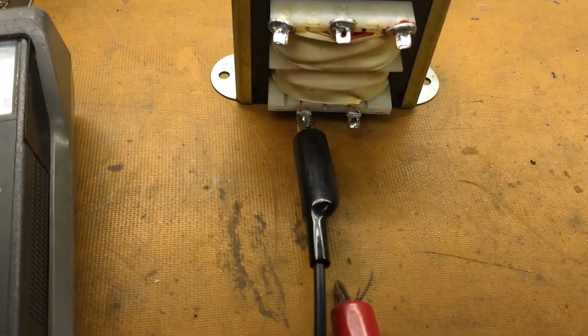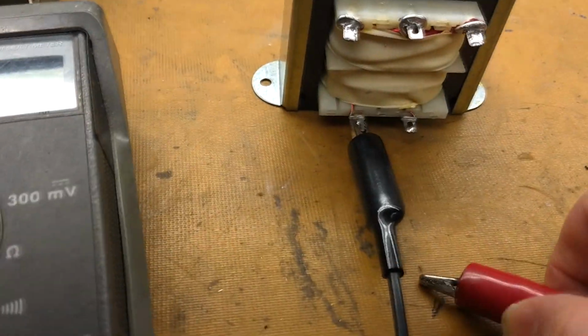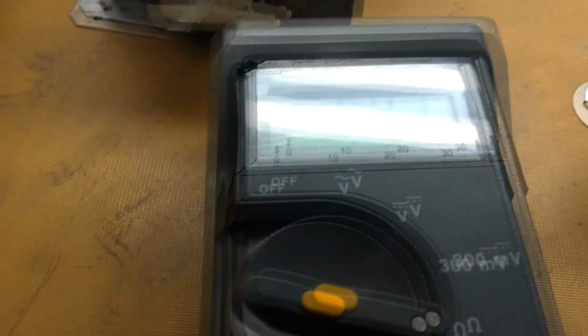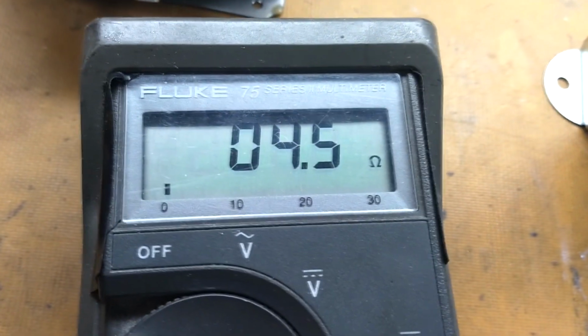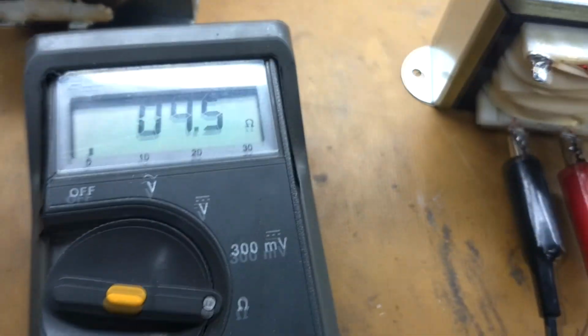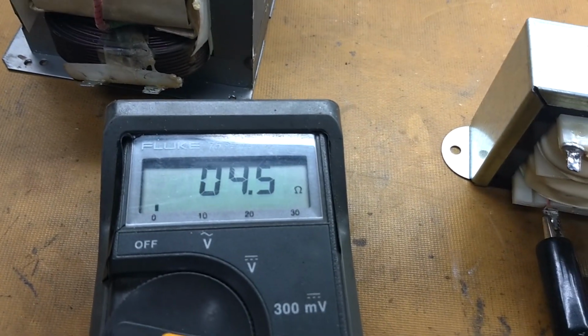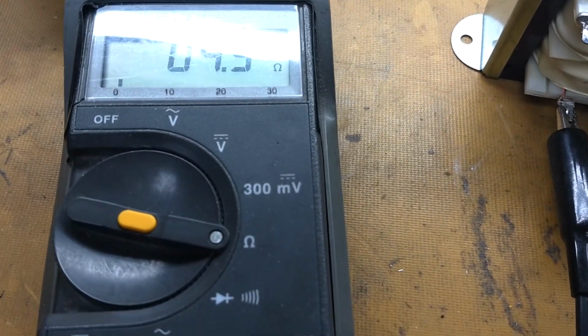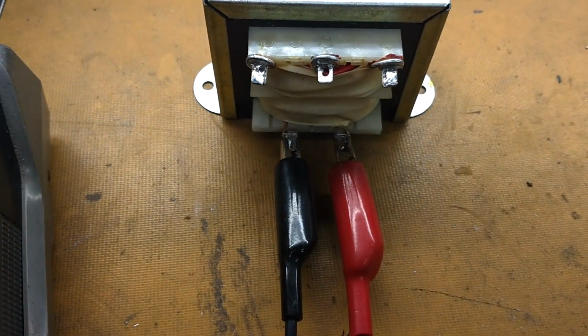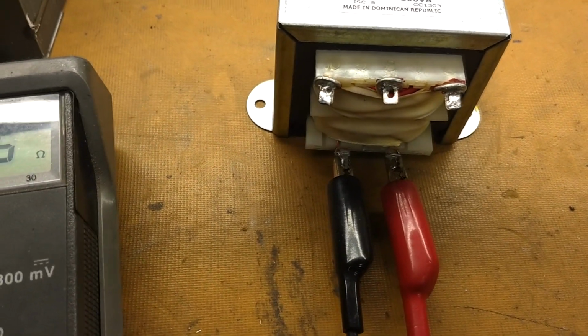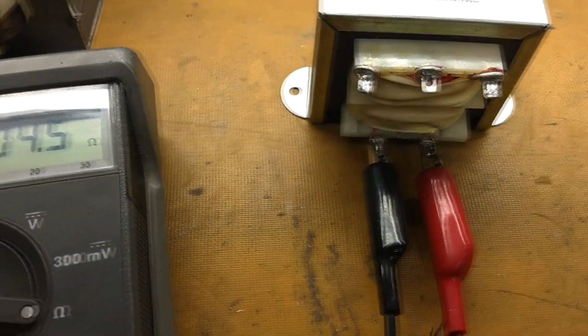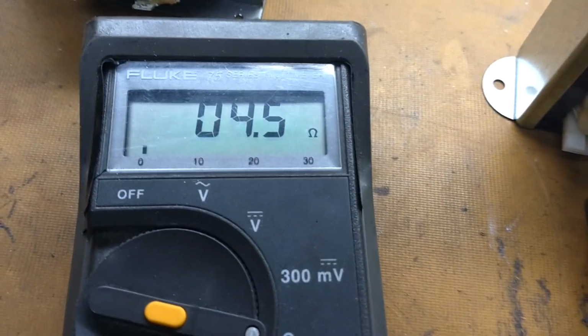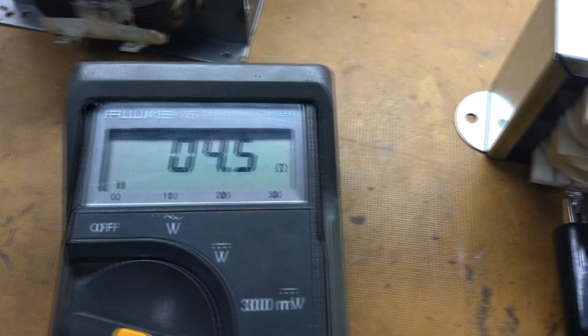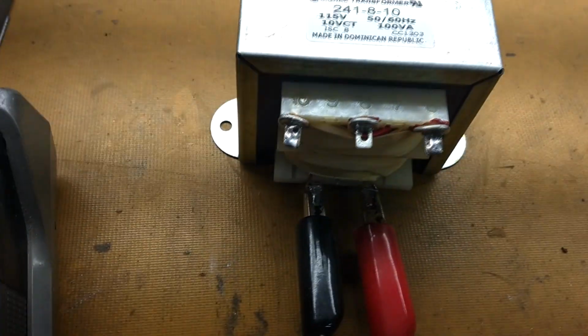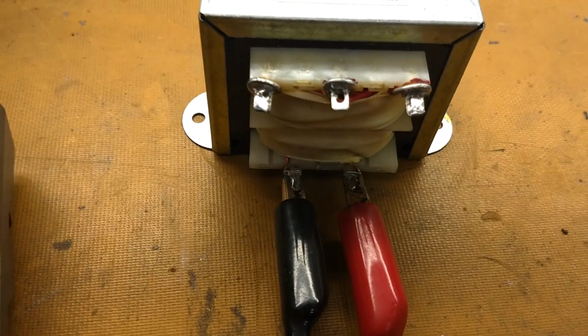Let's measure the primary resistance of this transformer. I have a meter here set on ohms, and we're reading around 4.5 ohms. Now, previously I measured my test leads and they were 0.1 ohms. But a thing to be aware of, if a transformer is operated under full load conditions for a long period of time, it'll get pretty warm. And this resistance will actually go up by as much as 40%. So we may be approaching 6 ohms on a fully hot transformer.